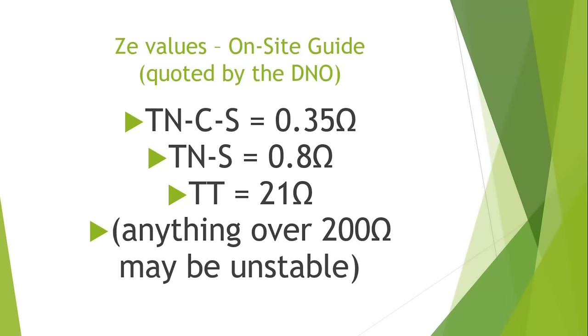The values quoted in the on-site guide by the distribution network operator are as follows. For a TNCS earthing system, we need a maximum ZE of no greater than 0.35 ohms. For a TNS system, the maximum value of ZE is 0.8 ohms. For a TT system with an earth rod, they recommend 21 ohms, but they can vary. The on-site guide says that anything over 200 ohms may be unstable, so a TT ZE is going to vary.